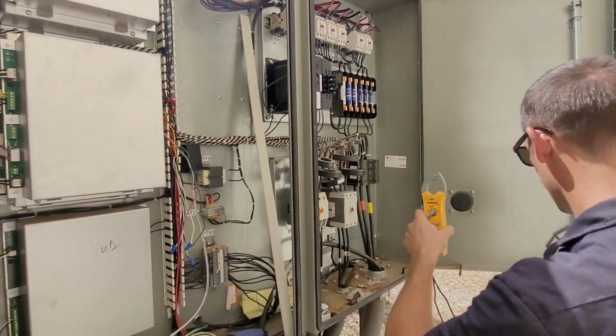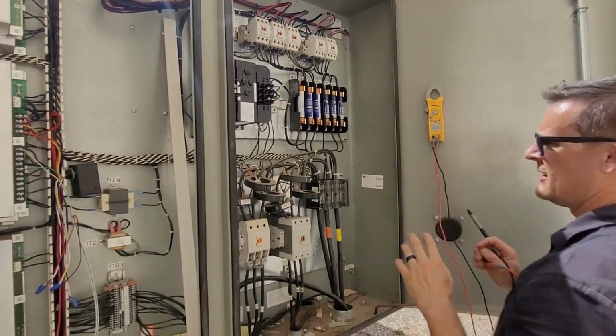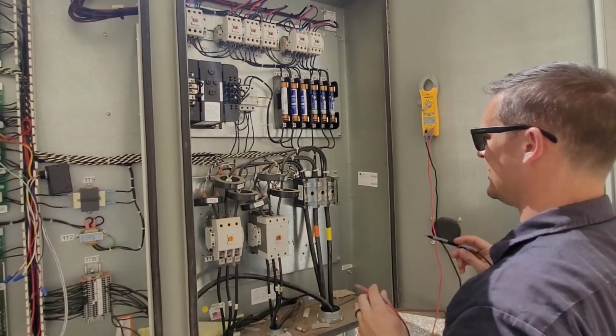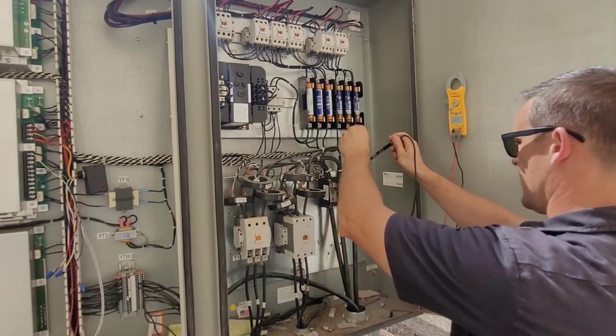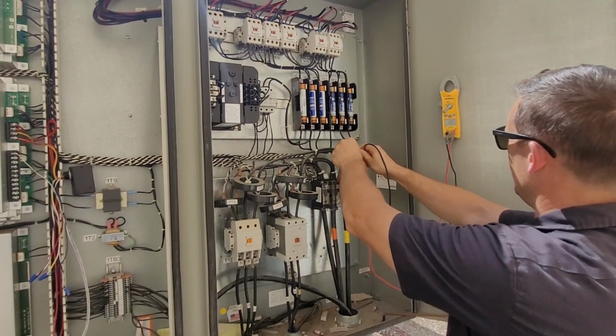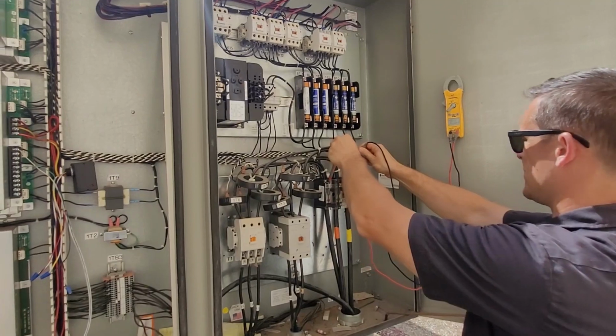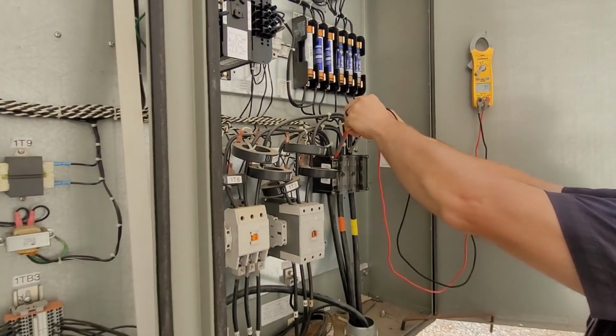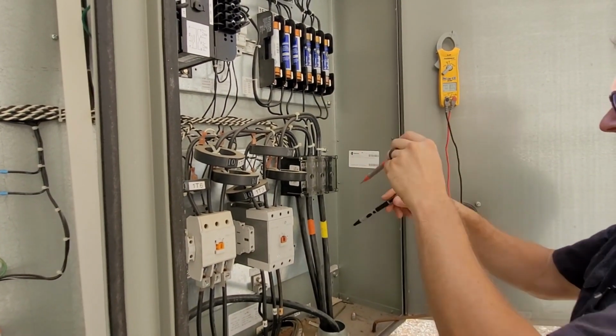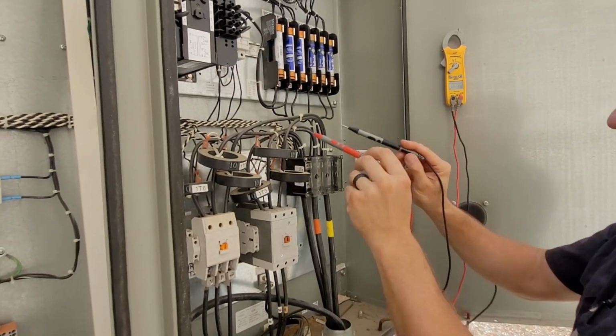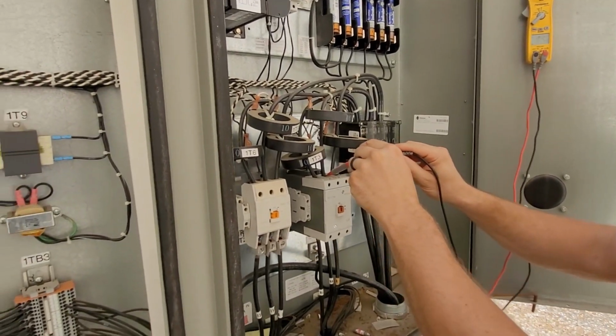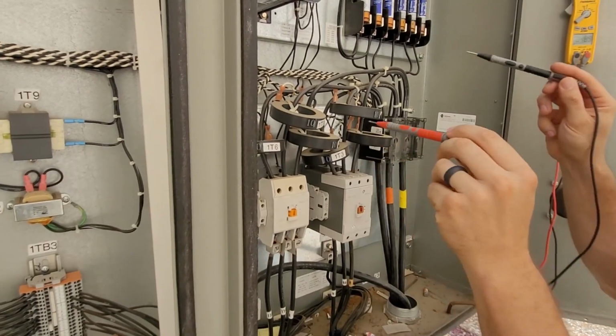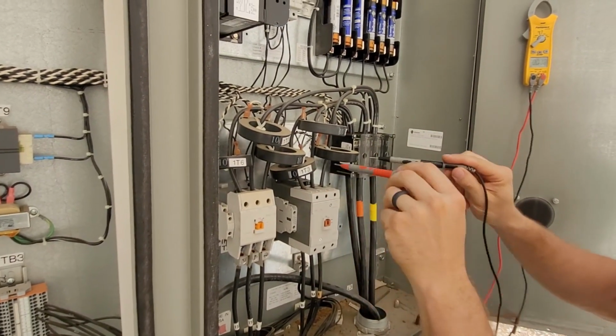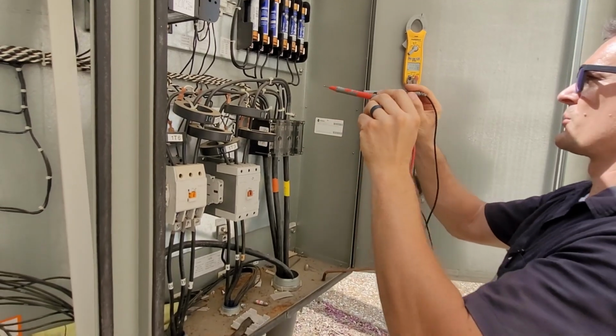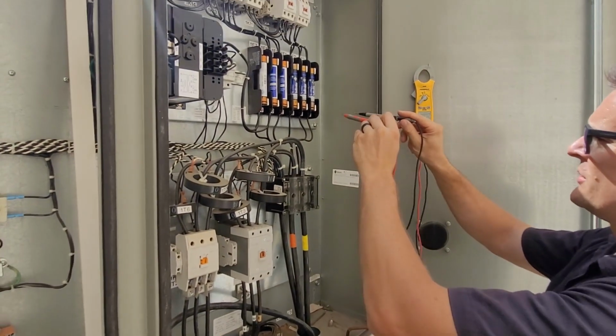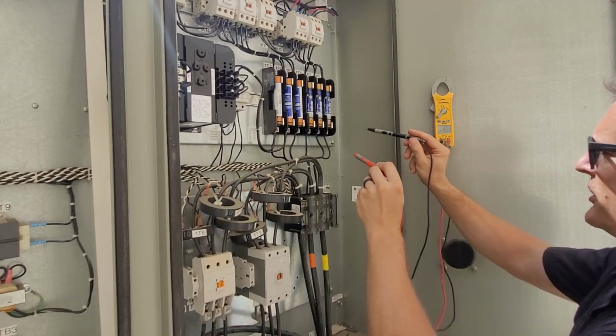So then I'm moving over and I'm looking at the high voltage side where everything comes in. So I start at the beginning where it comes in from the disconnect. 480 volts. Check between all 3 of the legs. 480, 480. So all 3 legs coming in are good. I checked over here just for fun, but these actually just go out to the compressors. So that's not going to be the control transformer stuff. So really, the next thing to do is to check all these big fuses here.